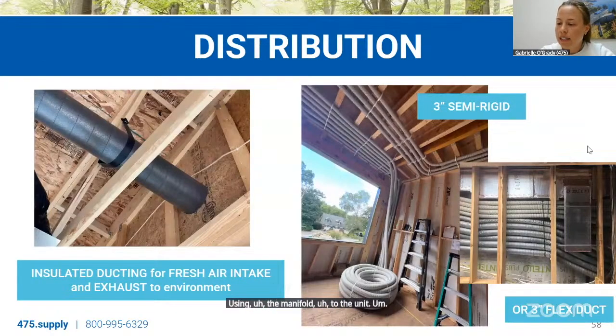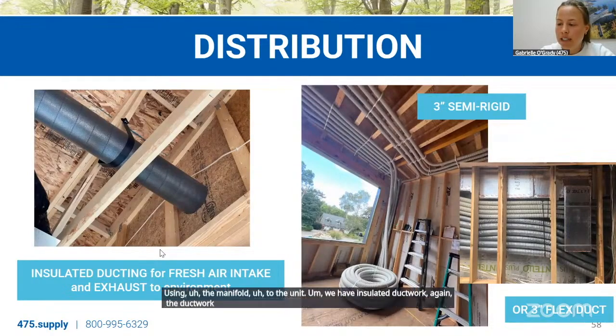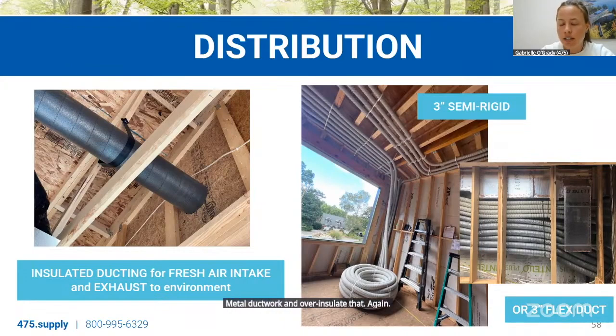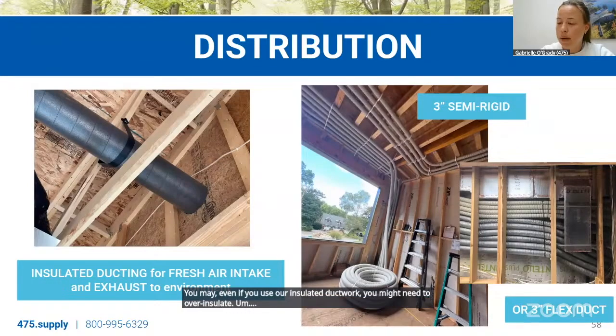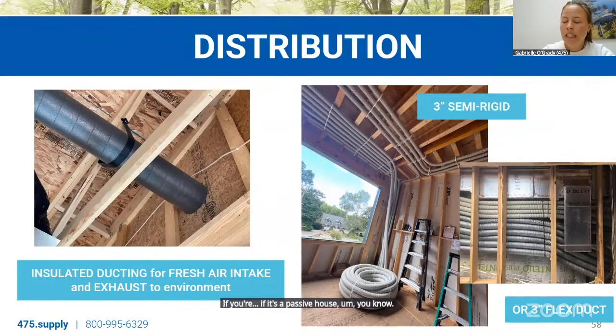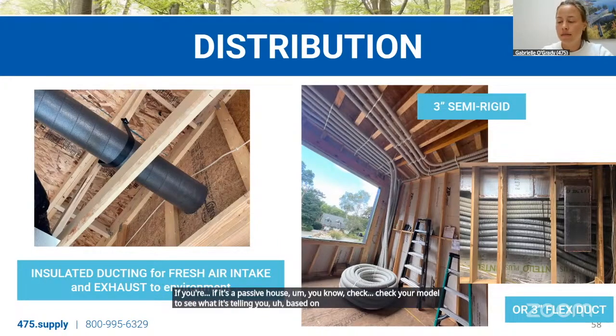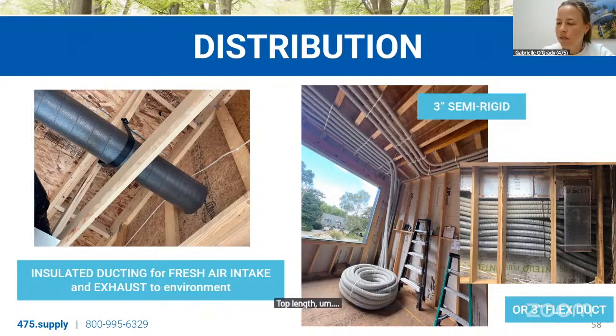We have insulated ductwork. Again, the ductwork needs to be insulated for that fresh air intake as well as the exhaust to the environment. So whether you use our insulated ductwork or you use metal ductwork and over insulate that, again, if the ducts are very long, even if you use our insulated ductwork, you might need to over insulate. If it's a passive house, check your model to see what it's telling you based on that duct length for insulation values. But keeping those short is key.